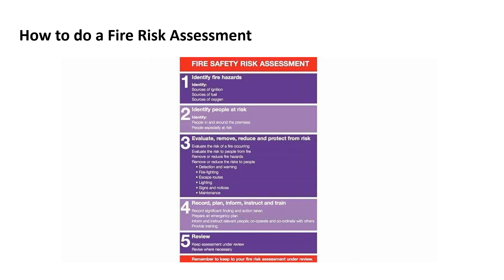Step two is identifying people at risk — people in or around the premises or people especially at risk. Step three is evaluating, removing, reducing and protecting from risk: we assume a fire is going to start, we know we can't get the risk to zero, so what's in the building to help people evacuate safely? Step four is recording, planning and informing — recording the fire risk assessment, training, cooperating with people. Step five is to continually review. This five-step approach is generally accepted by government guides and many risk assessment methodologies.